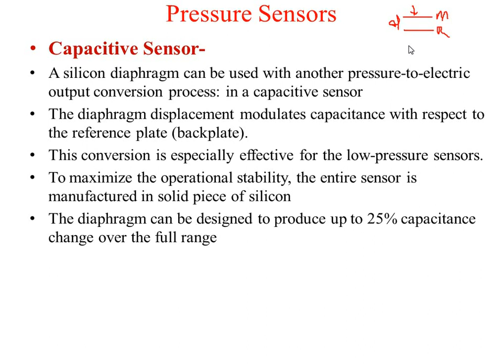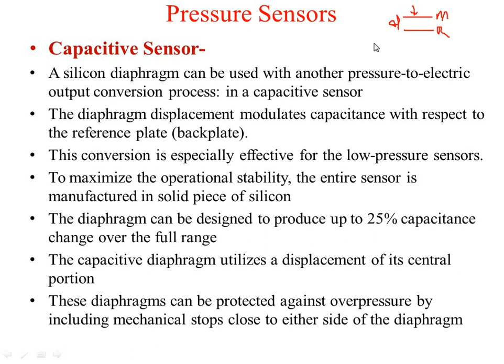These diaphragms can be protected against overpressure by including mechanical stops close to either side of the diaphragm. To avoid damage, whenever you are putting pressure on the diaphragm, there is a possibility that if you apply the highest pressure, there will be permanent damage to the diaphragm. To avoid that, you can put a mechanical stop there, so that the diaphragm doesn't go beyond that. So you can maintain the elasticity or mechanical properties of that diaphragm. This is the principle used for protecting the diaphragm against overpressure.